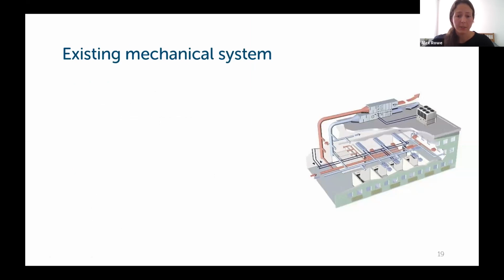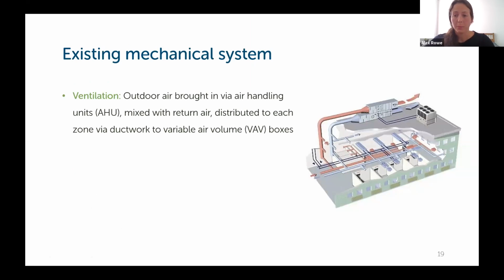So now let's dive into what they have to work with. For ventilation, this office brings in outside air through air handling units, where the outside air is then mixed with return air or recirculated air, and then distributed to each zone of the building via ductwork to variable air volume or VAV boxes. So this ventilation strategy is common in office buildings, but can also be found in hospitals, universities, and some larger high schools.